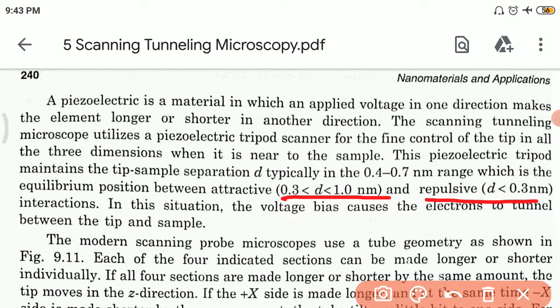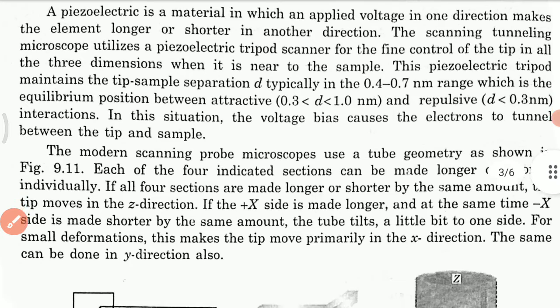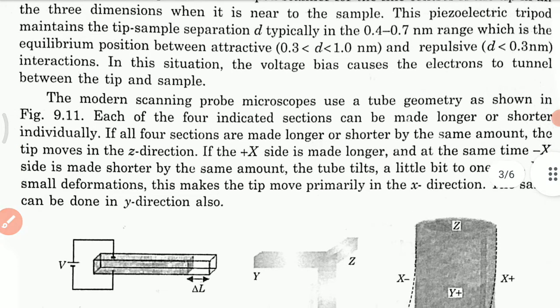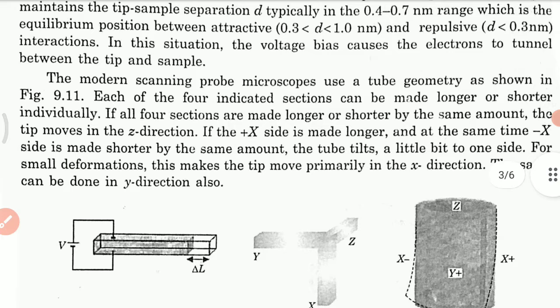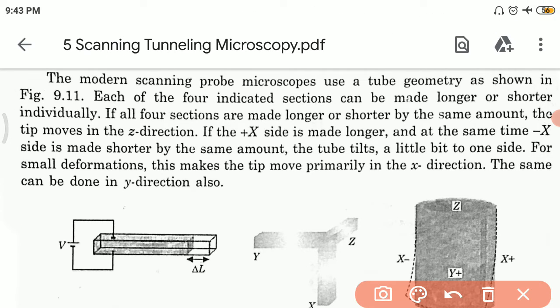So in this situation the voltage bias will cause the electrons to tunnel between the tip and the sample, so that it will be creating the tunneling current. Now the modern scanning probe microscope actually uses a tube geometry as shown in the figure.